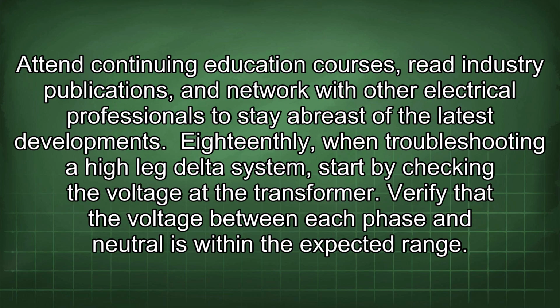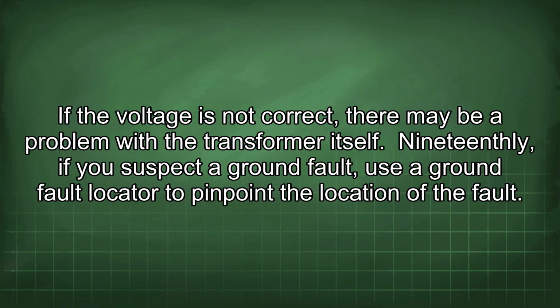latest developments. 18thly, when troubleshooting a high-leg delta system, start by checking the voltage at the transformer. Verify that the voltage between each phase and neutral is within the expected range. If the voltage is not correct, there may be a problem with the transformer itself.